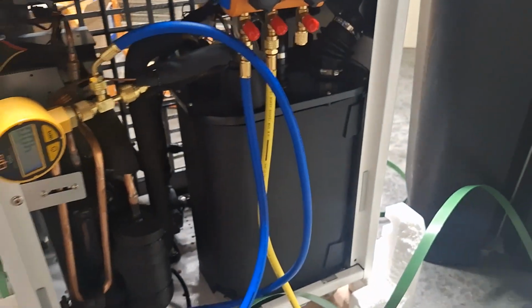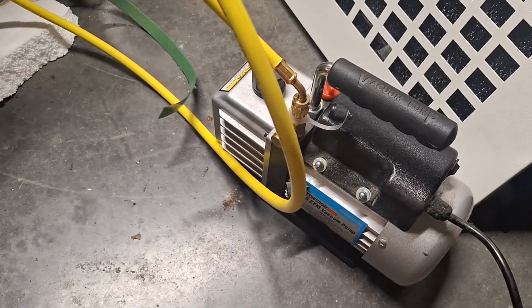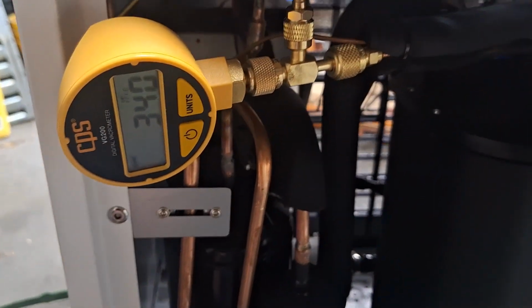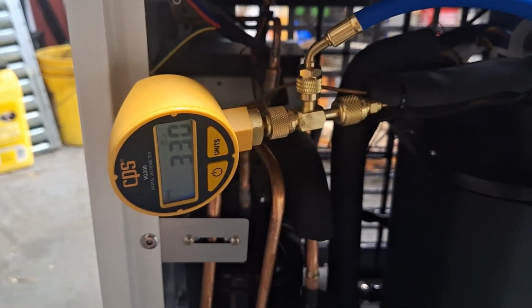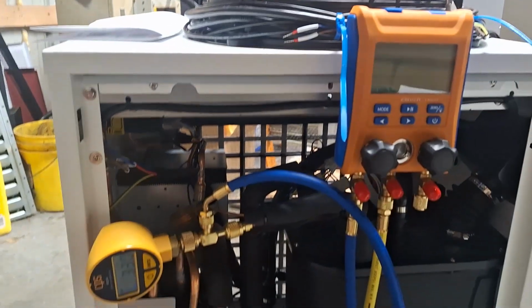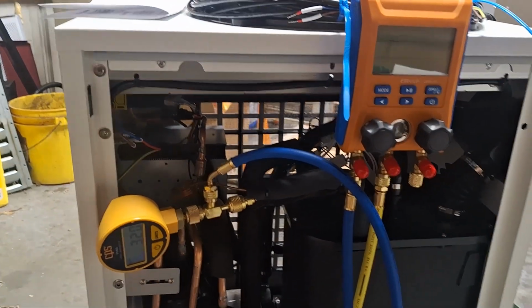Here I'm showing the vacuum gauge connected to the manifold gauge connected to the vacuum pump, just a Harbor Freight 2.5 CFM vacuum pump. Right now it's sucking all the moisture and air and anything that was in the lines right out.